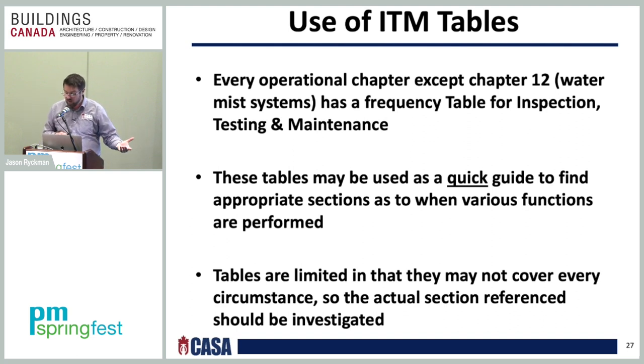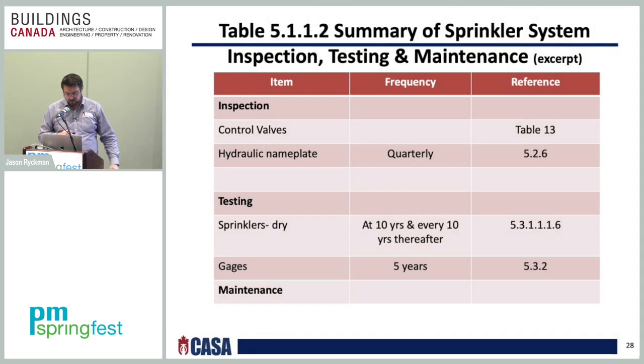But we would find that rule among the other reference sections from the table as well. So it's just a quick guide. Table 5.1.1.2, a summary of sprinkler system inspection, testing, and maintenance, gives you some of the items that you would find on a water-based fire protection system. And it'll tell you the different frequencies, basically the frequency of the specific item.